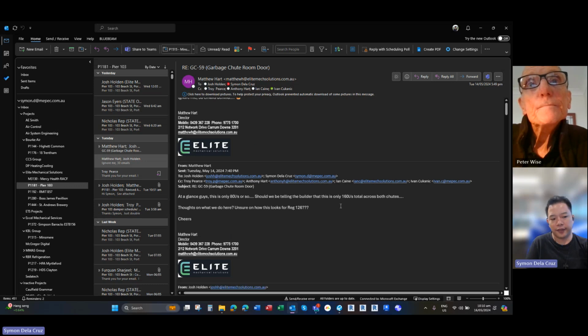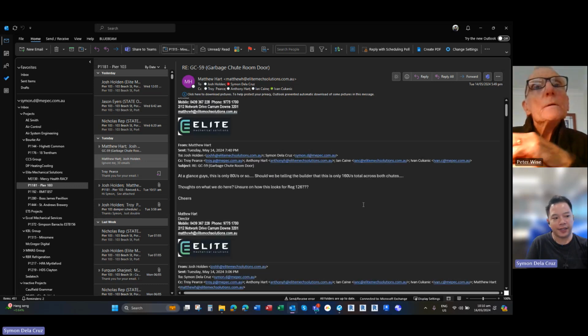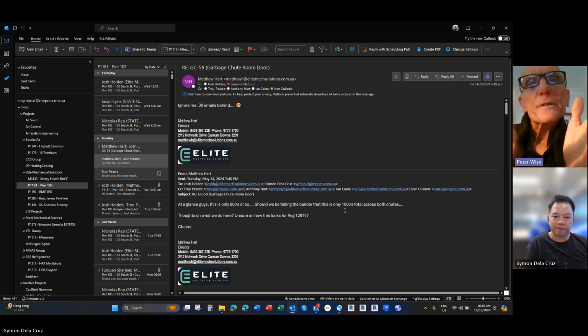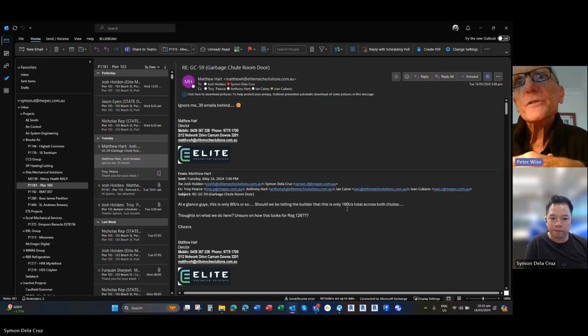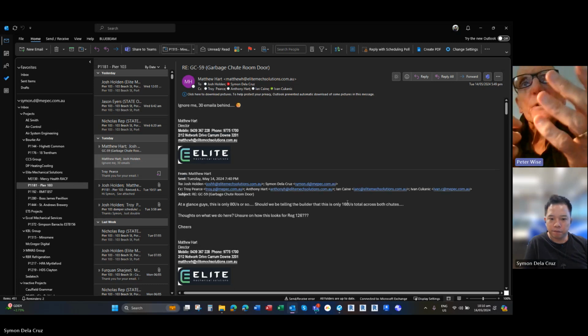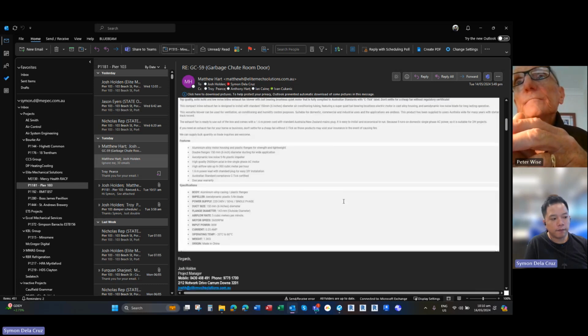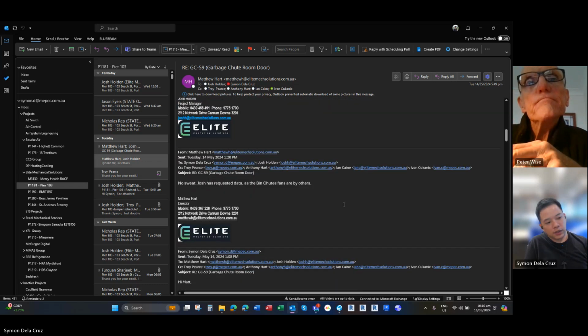They are arguing whether it's 80 or 100, it's not really going to affect the fan. The fan will be the same, and the grill would be the same, I would think. So it's not really going to change anything, but I think you need to have 100 to comply with AS 1668.